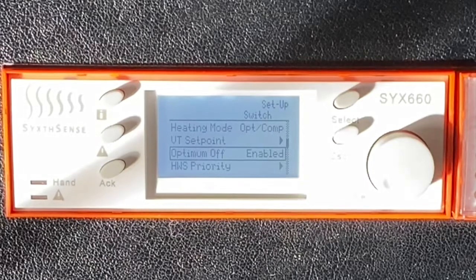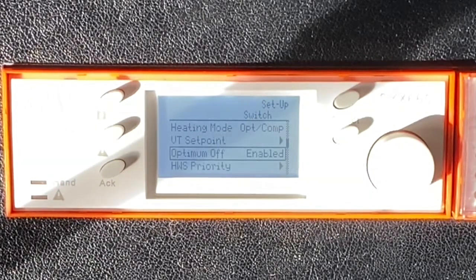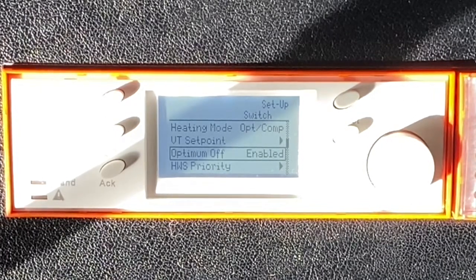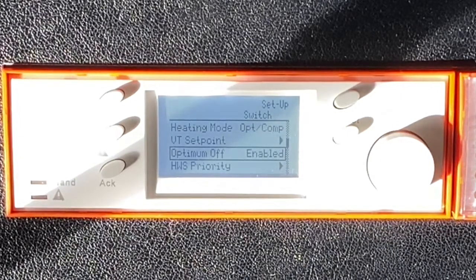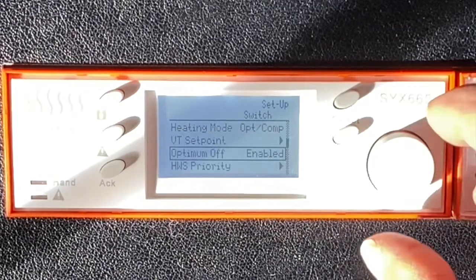So if we understand the dynamics of how quickly the building cools down, if there is a surplus of heat before the end of occupancy, if we can maintain it within 1 degree of the target set point by the end of occupancy, then we can utilize that, and we can switch the heating off early and obviously save some money for the client.